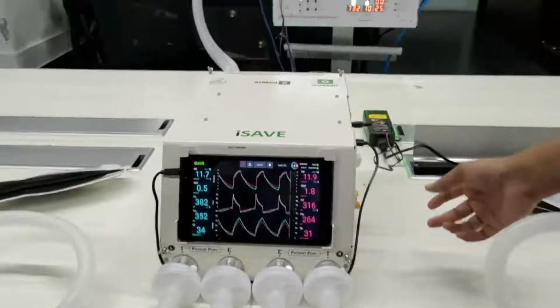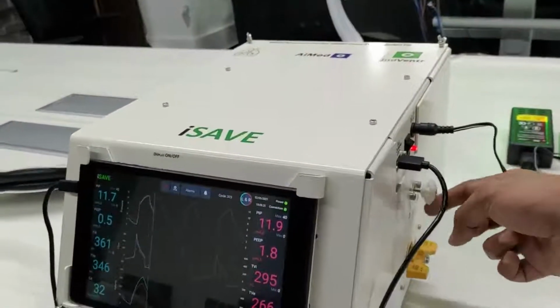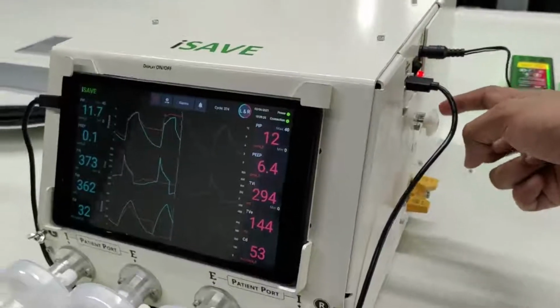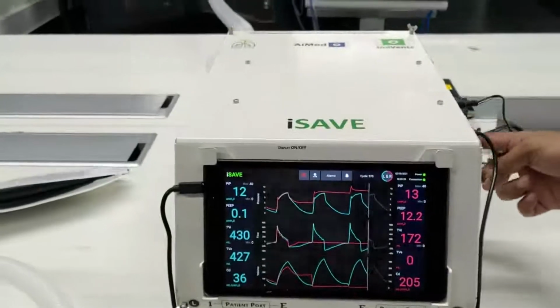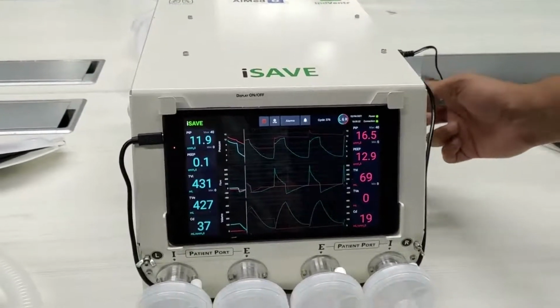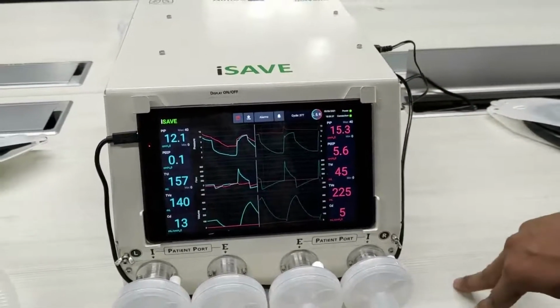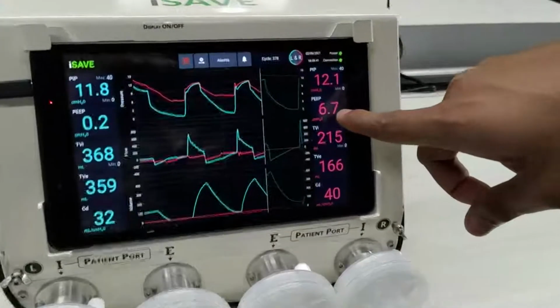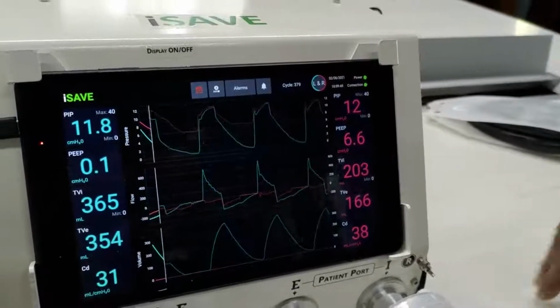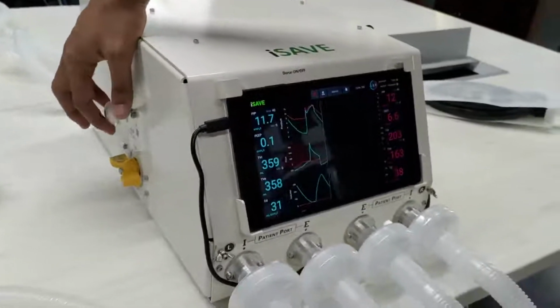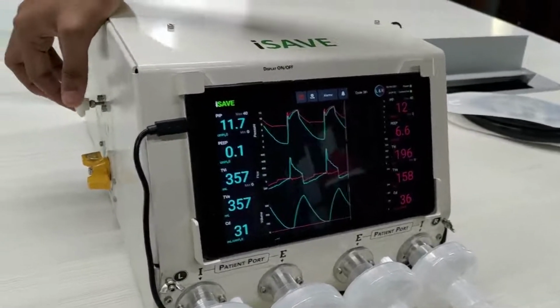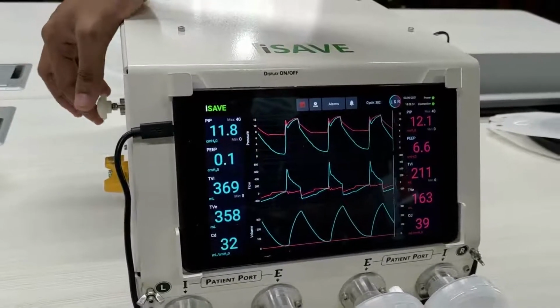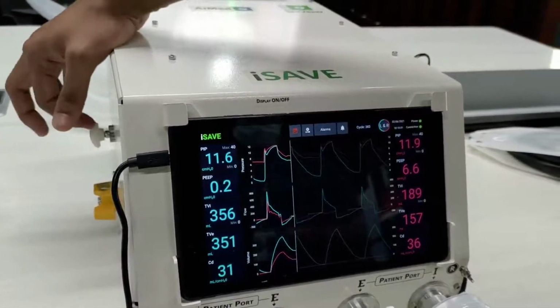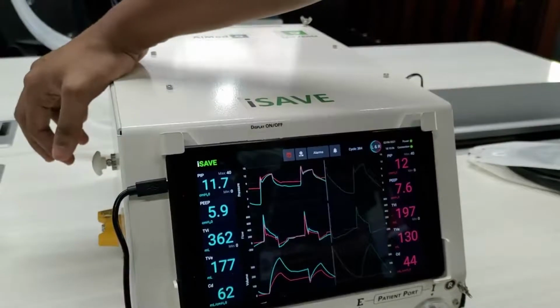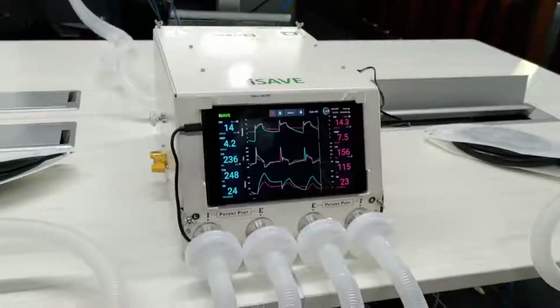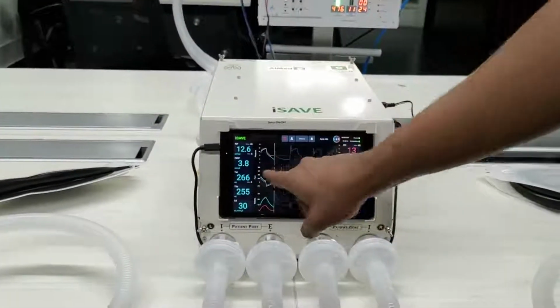So in pressure control mode, we won't be rotating this valve. We can adjust the PEEP over here. So I'm now increasing the PEEP for the right patient. Let's reduce that a bit. I think that was overkill. Okay. So we can see the graph for pressure. So we're getting a PEEP of 6.7. Similarly, we can adjust for the left patient. So let's increase our PEEP. Yeah. So now we have two different PEEPs for each patient. We got 3.8 and we got 7.5.